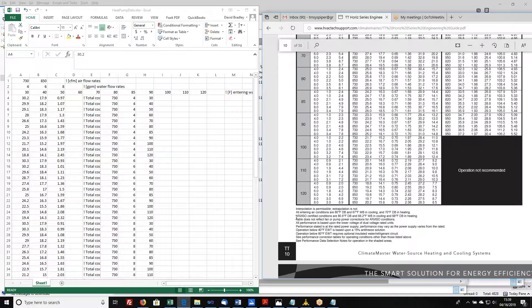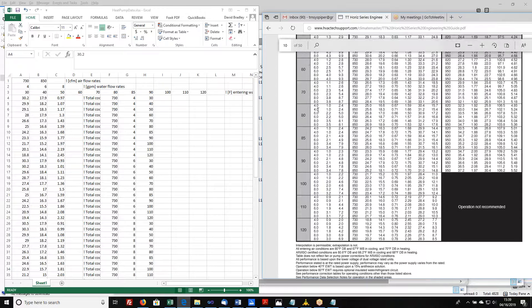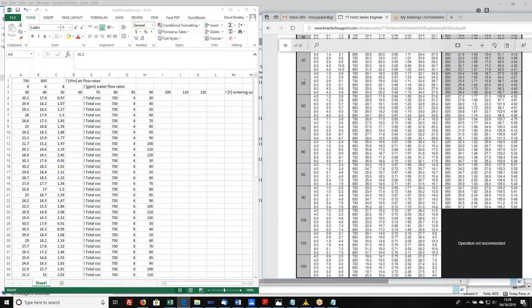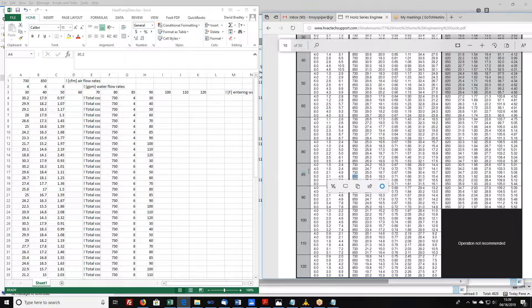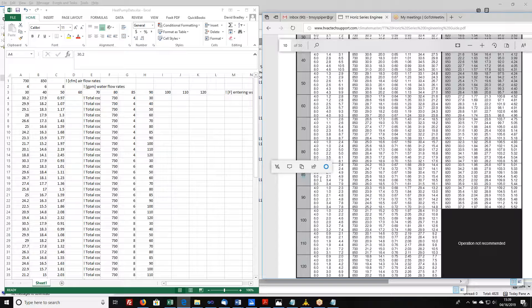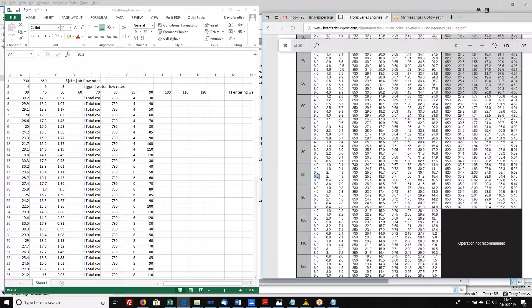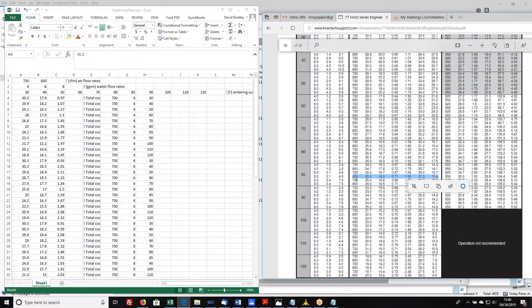So if you look down here at the bottom, it's talking about an ARI standard and an ISO standard for what the entering conditions are. You can also sometimes guess because there'll be one value that's sort of outside of the usual pattern. So we're going up by 10 degree increments here, and all of a sudden there's an 85, a 5 degree increment. That's a good guess there that that would be the rated condition, that that's why they put that in there. So we know it's 850. We know it's 85. I didn't find anything in this data file about the rated GPM. But here actually what I did was I was able to look at the specification sheet that I was given. And this particular unit was called out with about a 6 GPM flow rate. So I'm going to guess this point right here is the rated condition. 850 CFM, 85 degree entering water temperature, and 6 GPM on the water side.